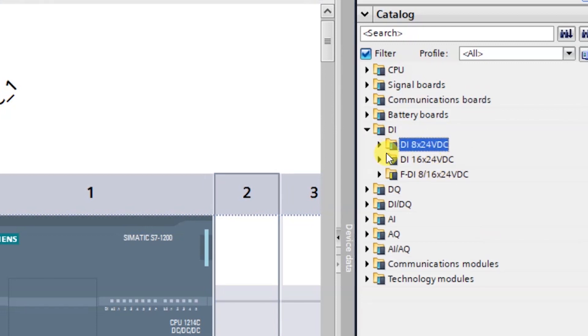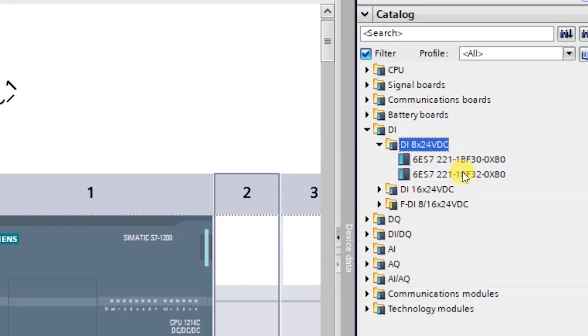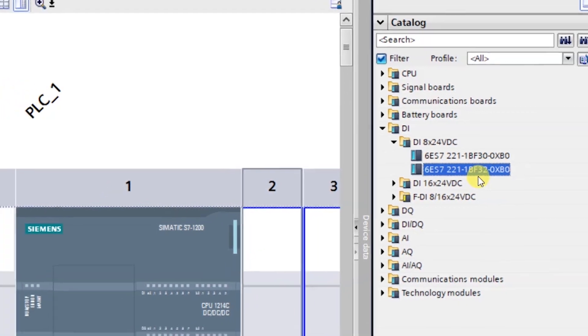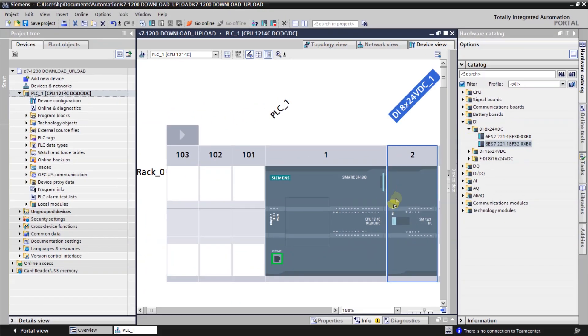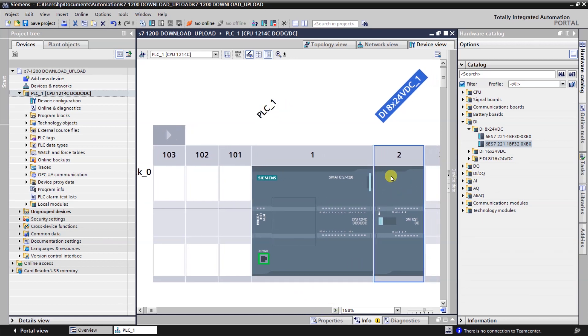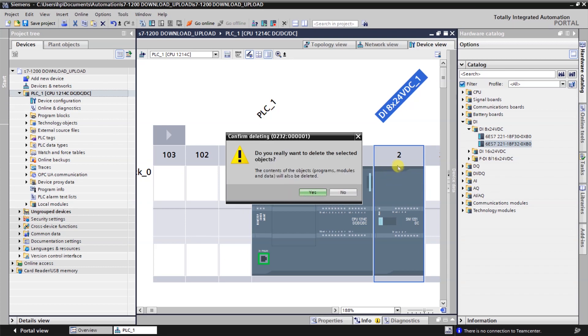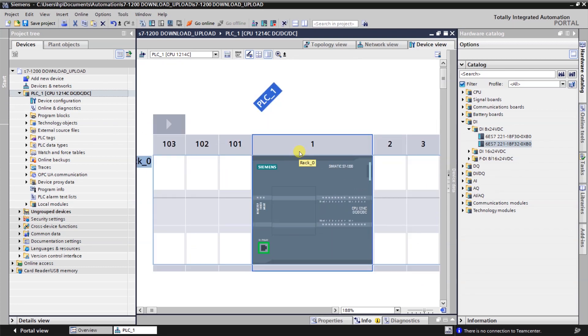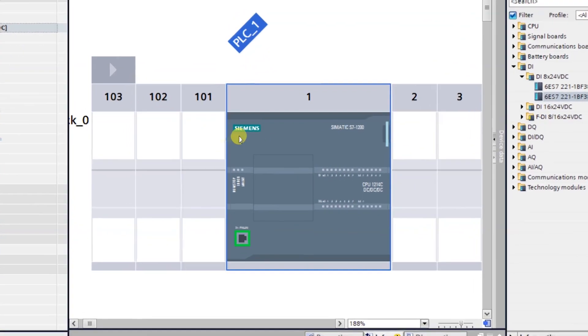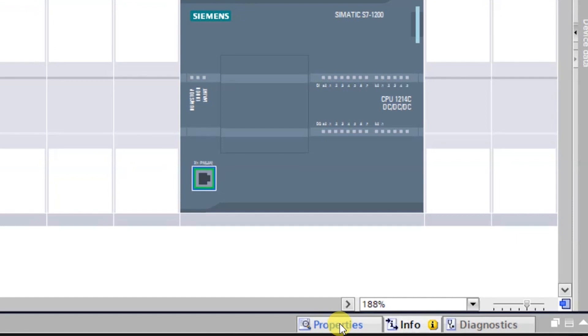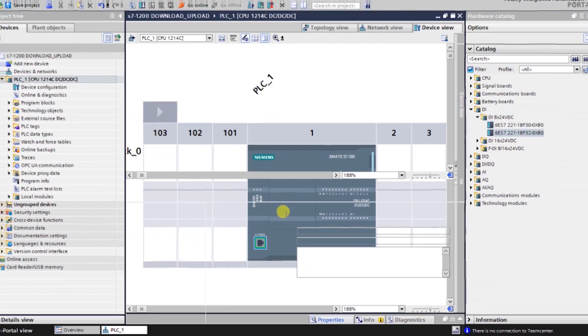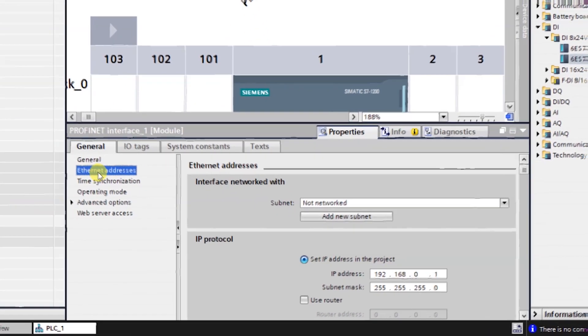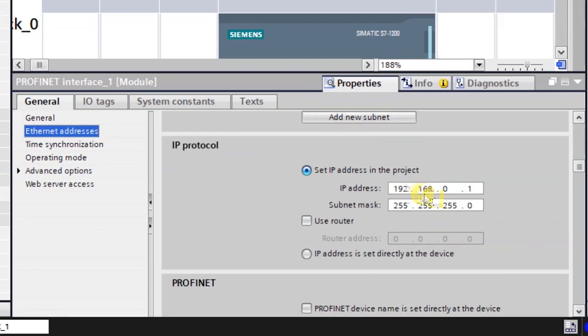To add a module, use the catalog on the right side of the screen. For example, click on DI (digital input), choose the input count — 8 inputs, 16 inputs — then select the catalog (MLFB) number and drag and drop it into the configuration. This is how hardware configuration is done. We also need to configure the Ethernet address — click on the Ethernet module and open its properties from the bottom.